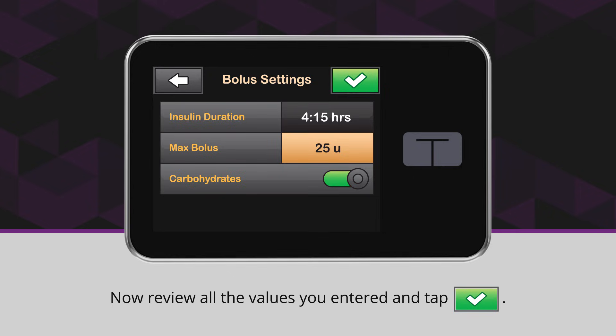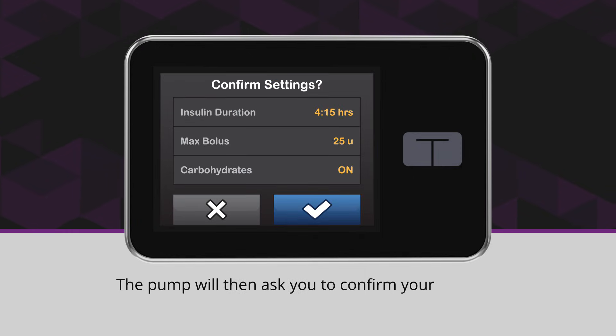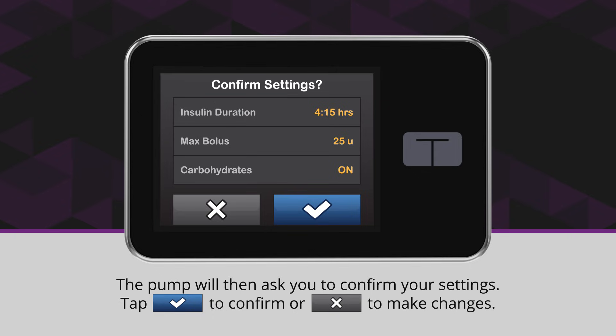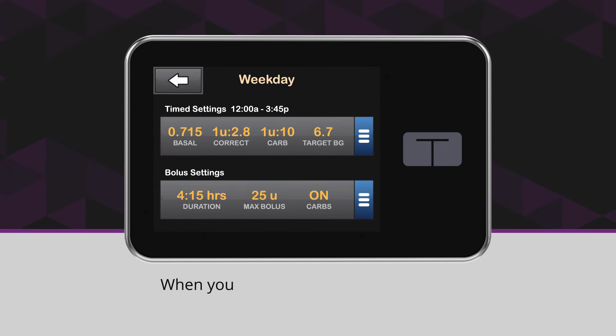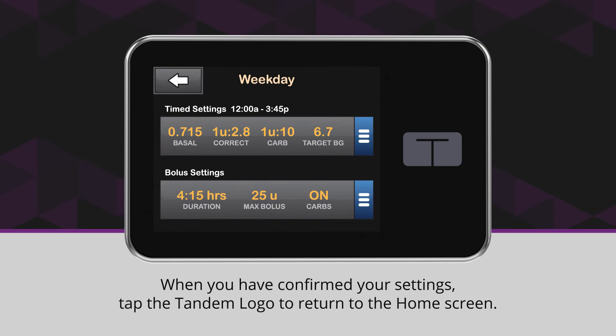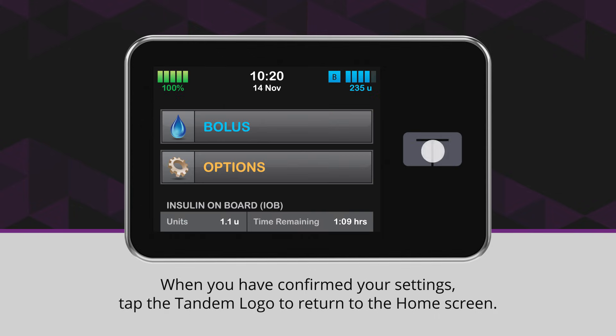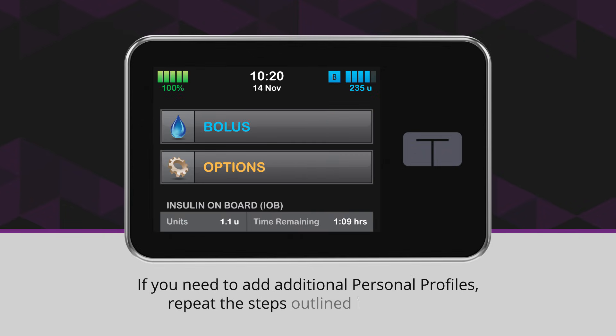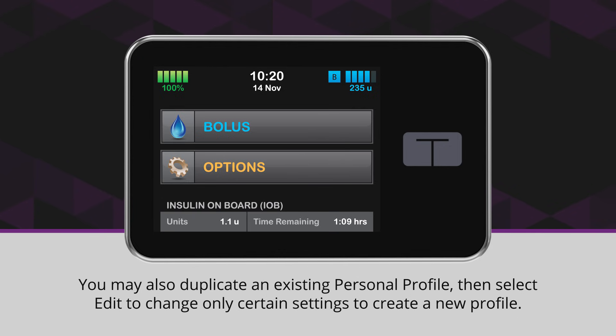Now review all the values you entered and tap the green checkmark icon. The pump will then ask you to confirm your settings. Tap the blue checkmark icon to confirm or the X icon to make changes. When you have confirmed your settings, tap the Tandem logo to return to the home screen. If you need to add additional personal profiles, repeat the steps outlined in this video. You may also duplicate an existing personal profile, then select Edit to change only certain settings to create a new profile.